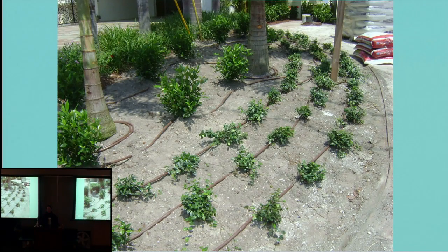I think one of the best ones, and this has been a while, was a pretty good sized system. It was a cemetery, and it was being fully irrigated, and up above was the water source, a 10-inch line that ran for about 5,000 feet. There was nothing put on the main line that would absorb any air or pressure. They turned on the pump, and there was no air relief, and the water came down to a closed gate valve. This entire main line, 5,000 feet of it, just shattered. That gives you an idea of how strong water is.